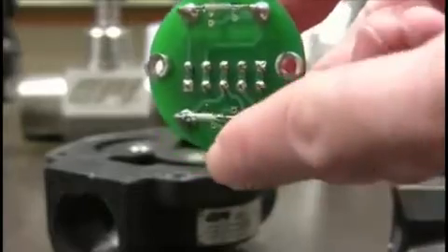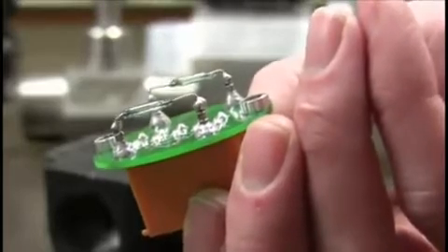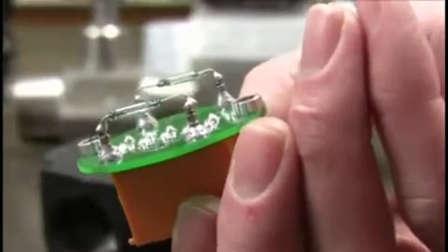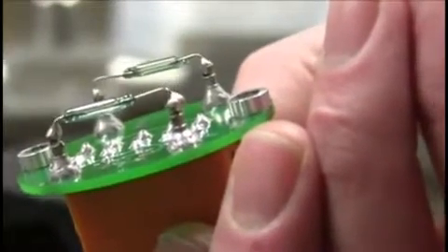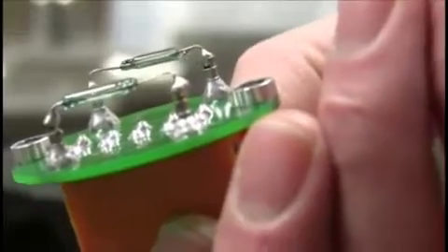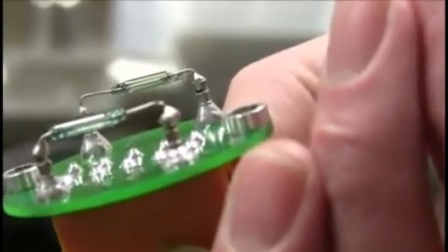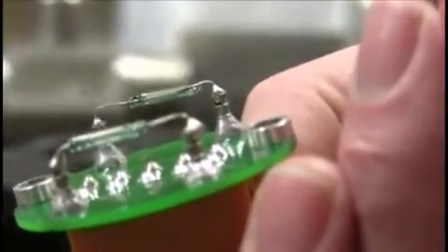Two reeds. One here is like a little glass tube, and inside that glass tube is a real thin wire, and that thin wire will bend down every time the rotor goes underneath it, and the magnet draws it down, and it'll touch a stiff hard wire, and that gives it continuity. And then once the magnet's gone, the reed or the thin wire straightens back out.